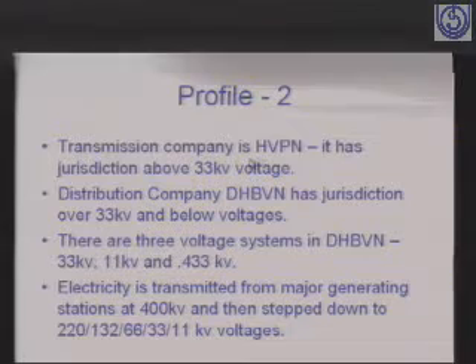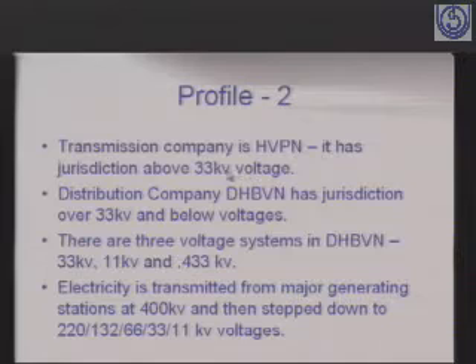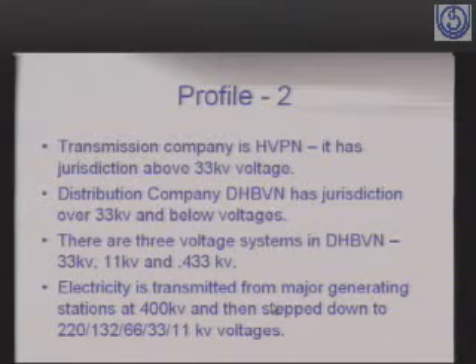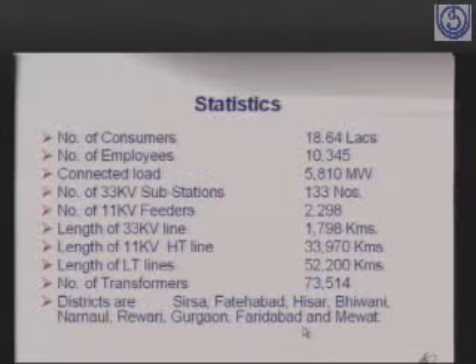There is one main transmission company, Haryana Vidyut Prasaran Nigam, which has jurisdiction over 33 kV voltage, and the distribution company has jurisdiction over 33 kV and below voltages. There are three voltage systems in this distribution company: 33 kV, 11 kV and 0.433 kV, that is 433 volts. Electricity is transmitted from major generating stations at 400 kilovolts and then stepped down to 220 kV, 132 kV, 66 kV, 33 kV and 11 kV voltage levels.